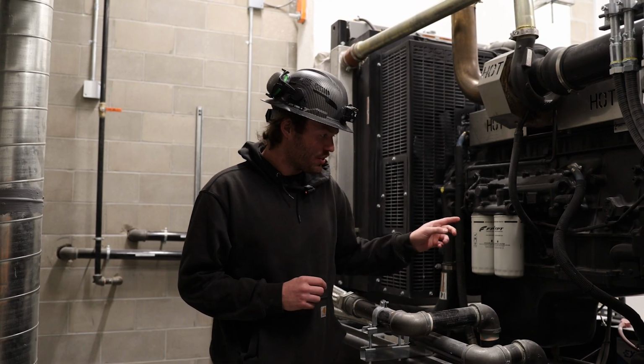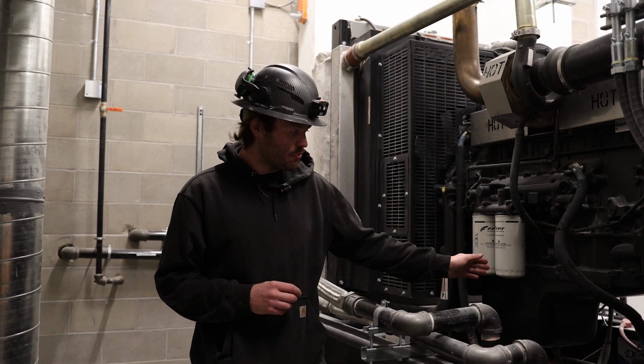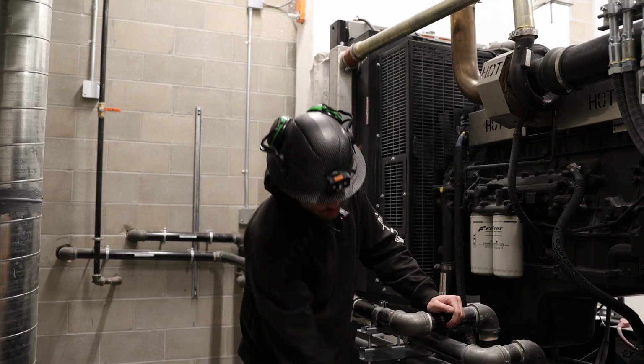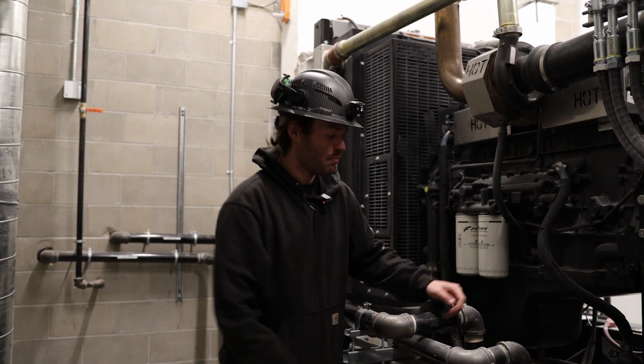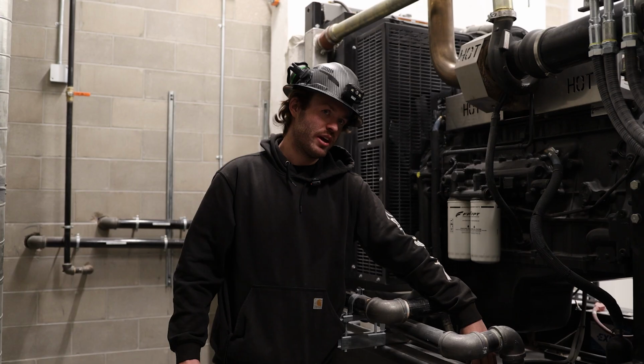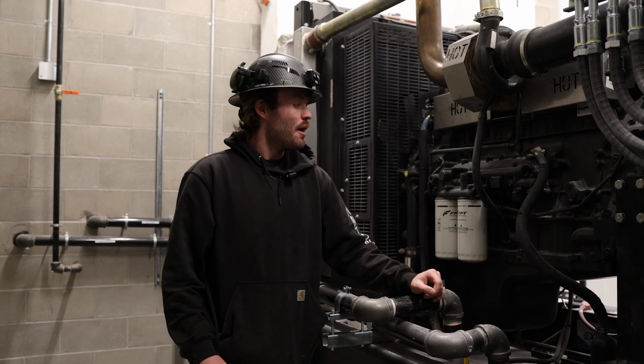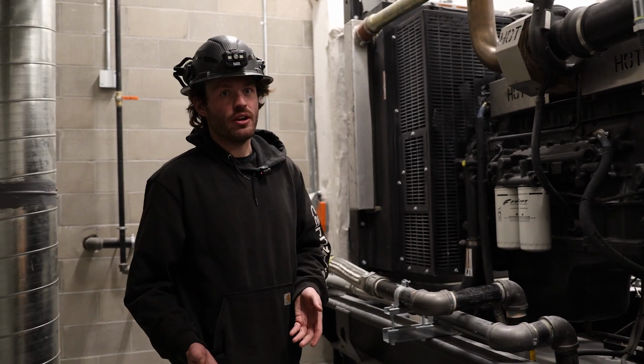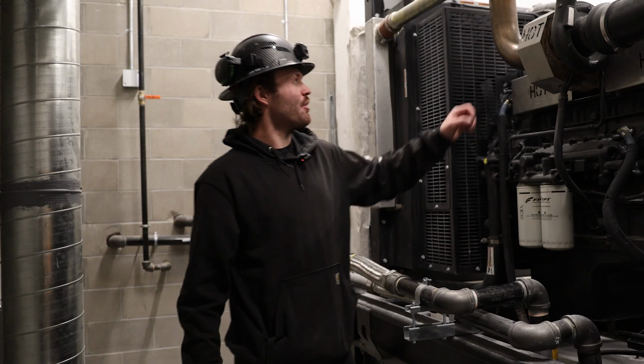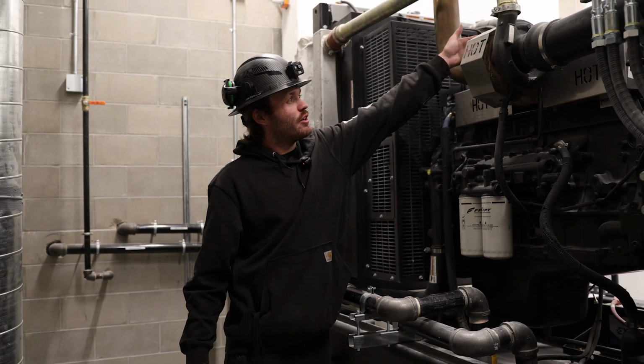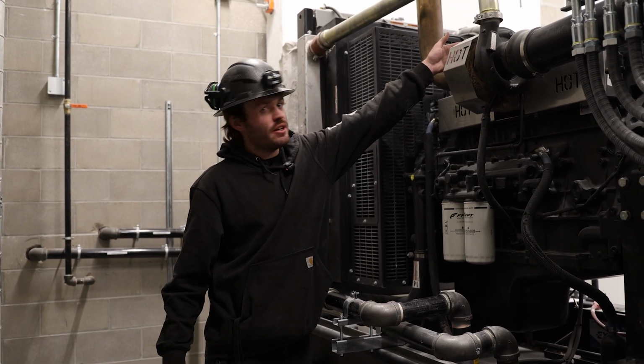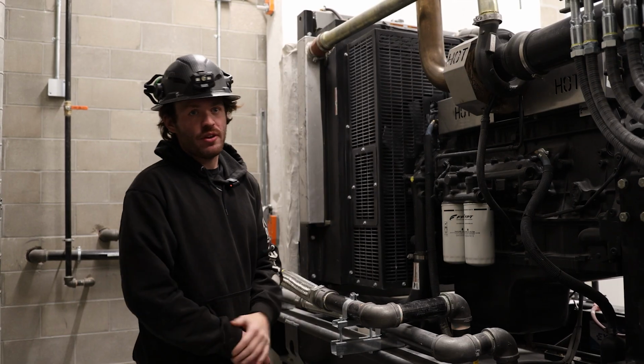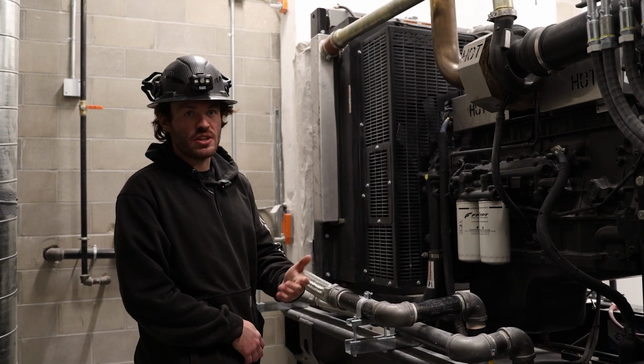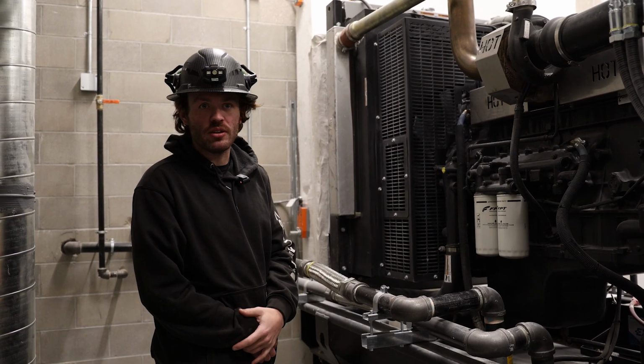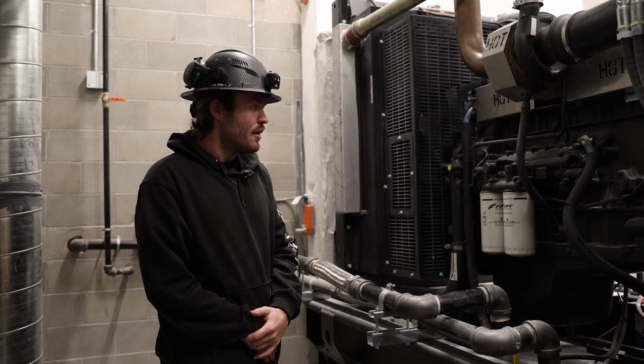I forgot to show it on the other side, but our oil drain tube goes out the bottom through the frame, and there is a ball valve just directly inside the frame. You can get a shot of that in a minute, but that's how you drain the oil out of the unit. Refilling is done through a cap on the valve cover directly behind the turbocharger here. It's a bright yellow cap. 15W40, decent quality diesel engine oil, for a diesel generator set.